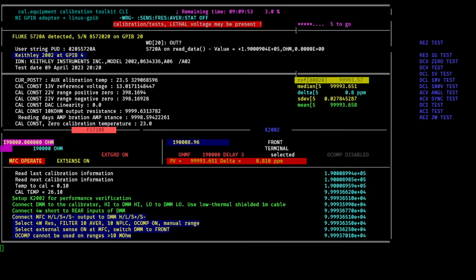Let's see if we can find a picture. Now it's 190 kilo ohm. Takes about a couple minutes per resistance value. And because the 5720 can source only fixed value resistances, there are around 18 or 19 of them. There is not much flexibility in choosing the value to test. So, I don't see many pictures of that disassembled. 190 kilo ohm is 0.57.